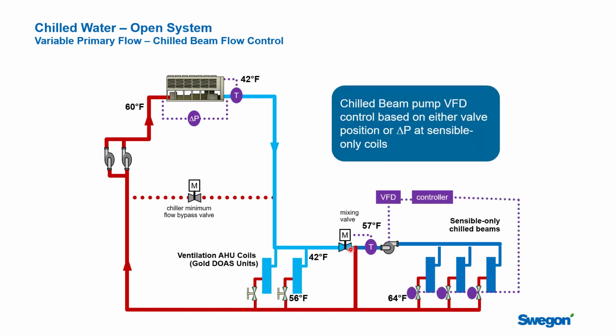We've talked about temperature, let's talk about flow. So we have a pump, it's going to be a variable speed pump. We're using two-way valves out at all the chilled beam control zones. And a typical way to do this would be to put a pressure sensor in the piping system. Good practice would be at least 2/3 of the way out to measure that pressure and speed up or slow down the pump to maintain system pressure.